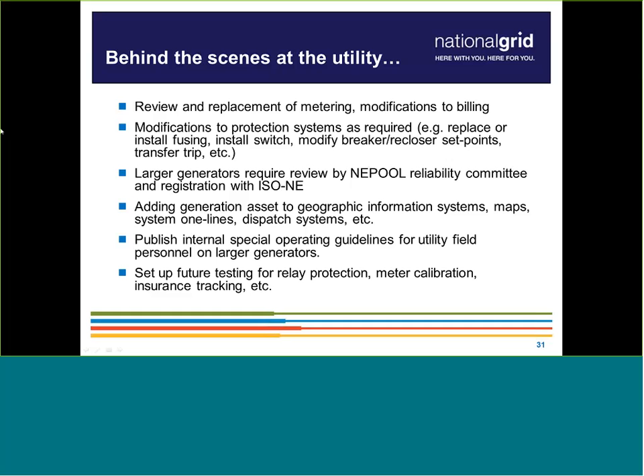If there are any maps we need to update for dispatch — if you're touching a substation, there's at least 150 drawings, so if we touch one of those items, every single piece of documentation has to be updated. It takes time to go through all of it, whether it's DTT, 3V0, or any regulator or settings changes. All of that has to be updated, and that takes time.